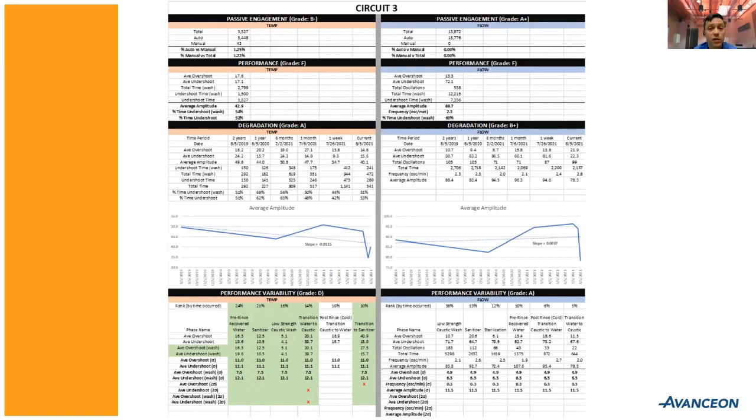And then in addition, many of these issues that we were able to identify on these initial 20 CIP loops actually affected more than 100 additional loops in various processes. So through our process, we were able to identify that. We've been making those changes through this initial remediation too. And then we'll be doing some further targeted analysis of those other process loops to see if there's more benefits that we can gain there as well.